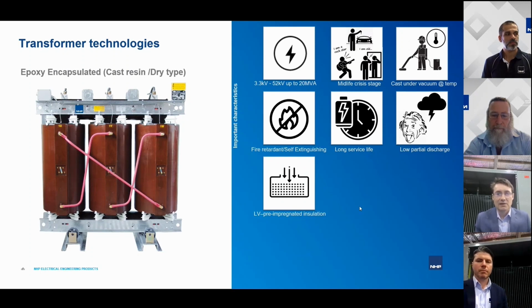Now, it's typically made out of pre-impregnated material, which is also cured in the oven and becomes like one solid structure. It's not the same as a HV winding. It's not a fully cast resin, even though for low voltage that's well sufficient, considering the voltage levels or the electric fields are much less in the LV windings. But it still provides very good mechanical strength for short circuit events. Having said that, there is a possibility to cast the LV winding fully in resin in the same technology as the high voltage winding, and that could be done for more extreme environments where you want the best possible environmental protection of that winding. But that, of course, would increase the cost.